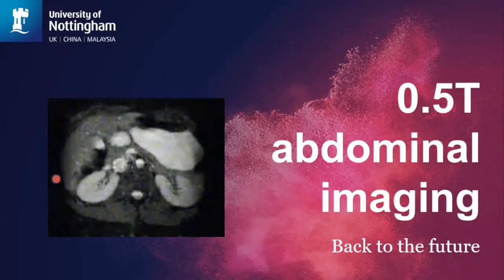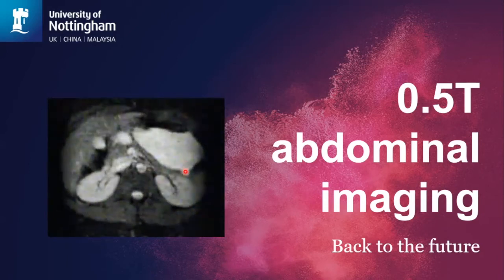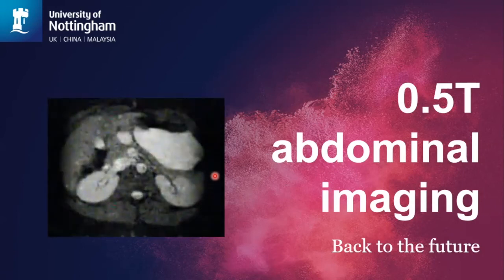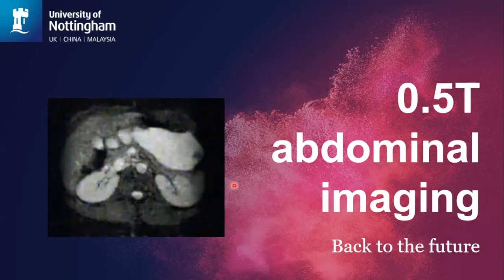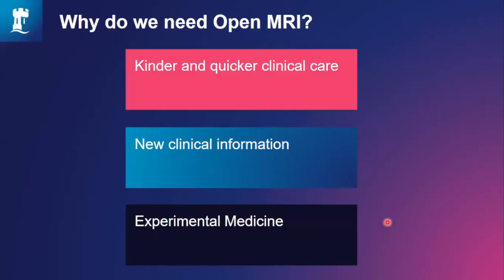This image is a half Tesla EPI scan of the stomach from around 1990. What this shows is that EPI works in the body, and that half Tesla can give you extremely important information. For me, this is back to the future. We're doing 0.5T not arbitrarily — we're doing it because it gives us an open MRI architecture. It's an open scanner from ASG Paramed.